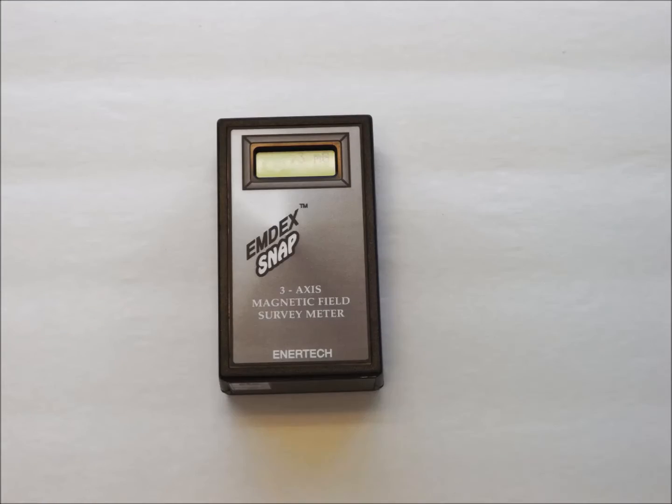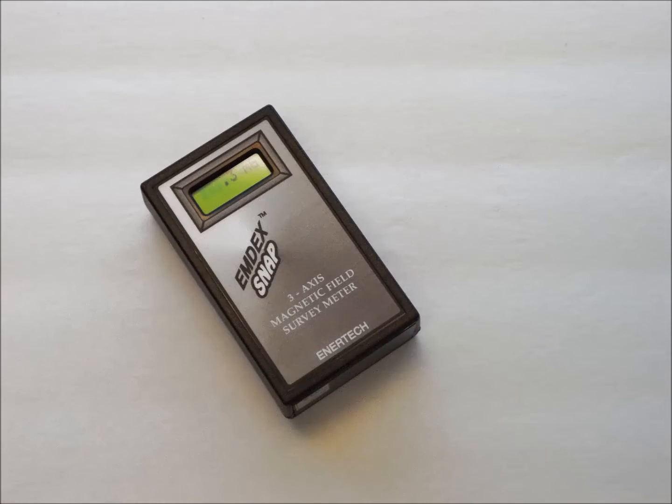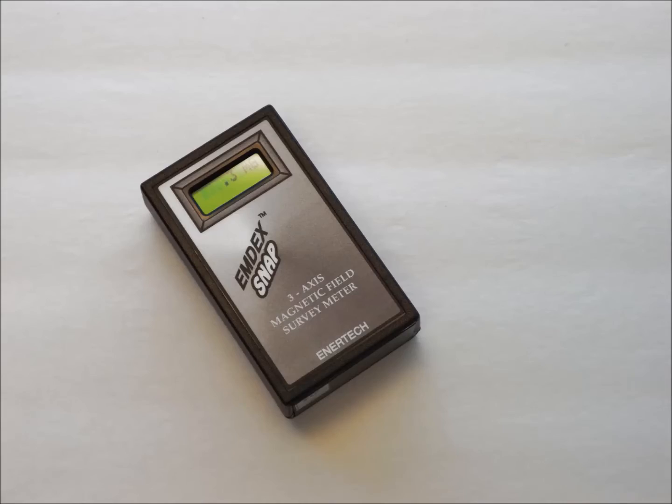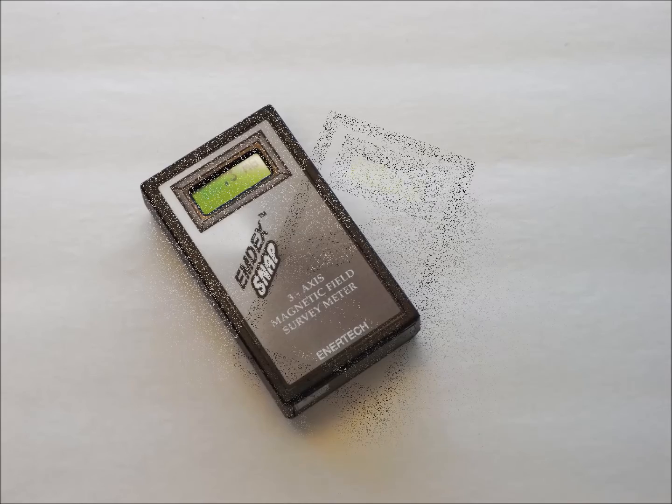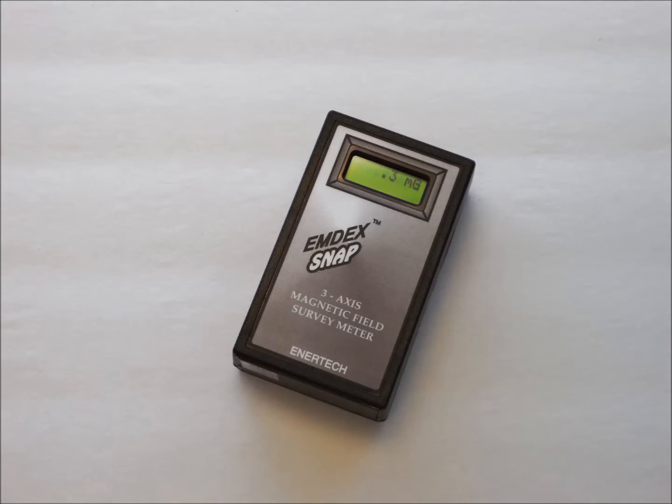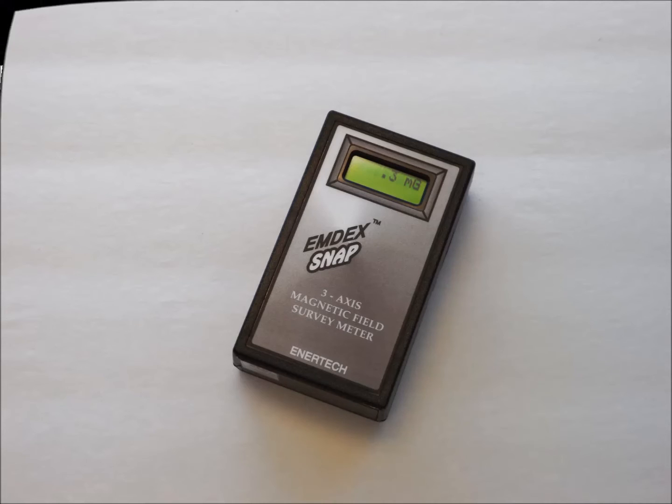A three axis meter has three sensors in it aligned at right angles to each other so it is always looking in all directions. The meter automatically interprets the output from the three sensors and reports the result as a single number. Therefore, this type of meter is always correctly aligned and no rotation is required to get a correct reading. This type of meter takes less time to use, but generally costs more than its single axis counterpart.